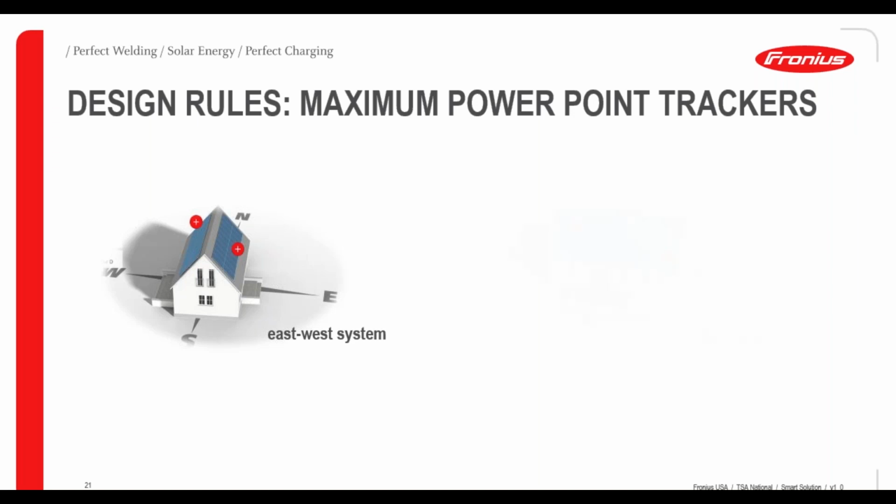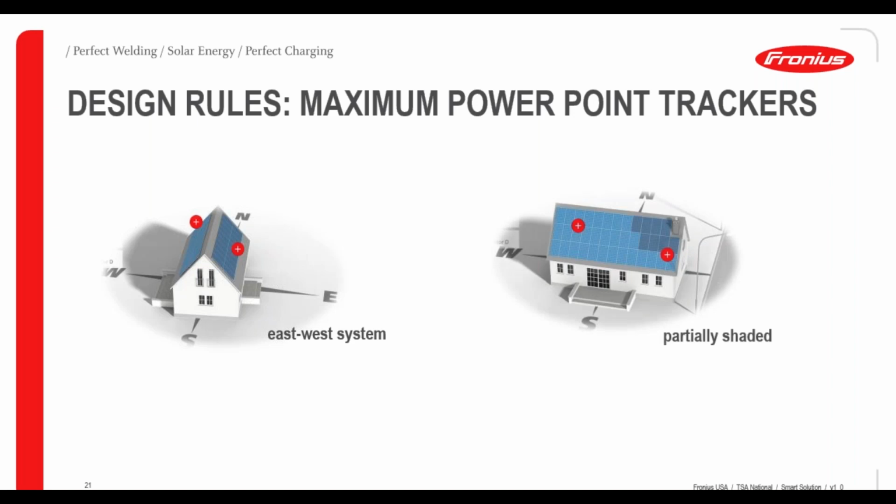So again, isolation of those different orientations is where the MPPT becomes very, very important in application. Right, about the second example. This one's a pretty large installation as well, so you're probably looking at a 10 kW system too. You're probably going to have one string on MPP tracker 2 with the shaded modules, and 3 strings on MPP tracker 1, splitting up the shaded area from the areas which are going to be unshaded.